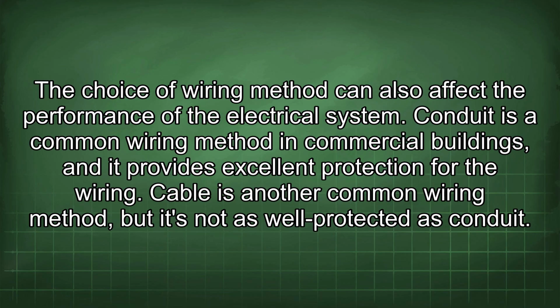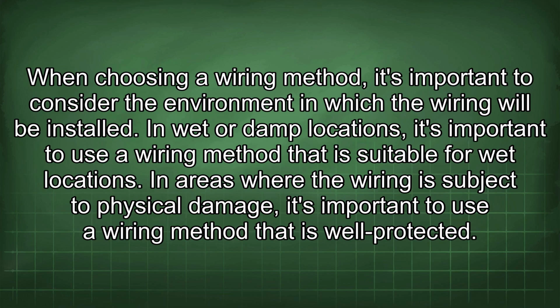The choice of wiring method can also affect the performance of the electrical system. Conduit is a common wiring method in commercial buildings, and it provides excellent protection for the wiring. Cable is another common wiring method, but it's not as well protected as conduit. When choosing a wiring method, it's important to consider the environment in which the wiring will be installed. In wet or damp locations, it's important to use a wiring method that is suitable for wet locations. In areas where the wiring is subject to physical damage, it's important to use a wiring method that is well protected.